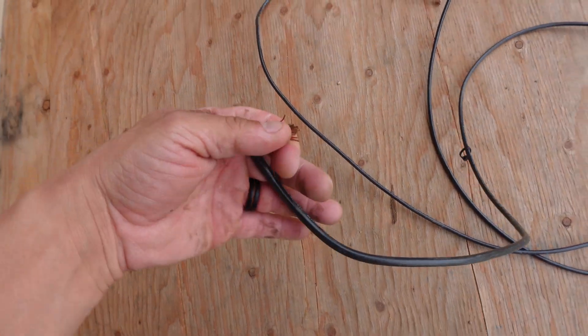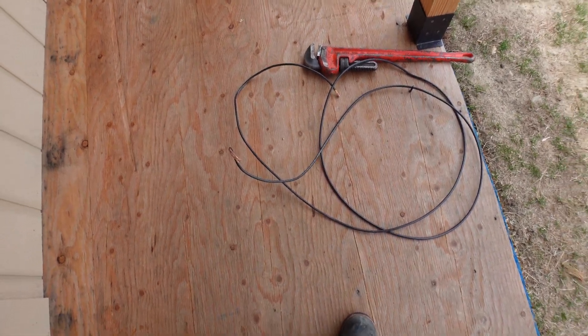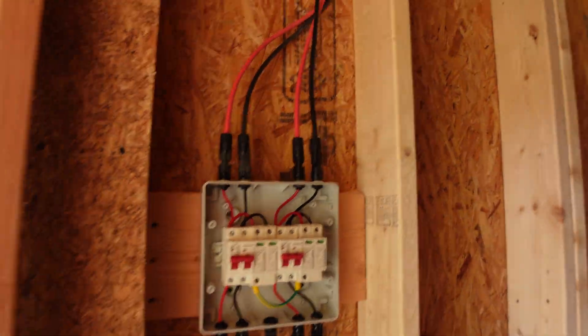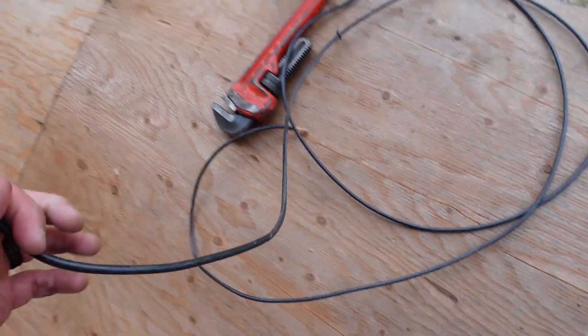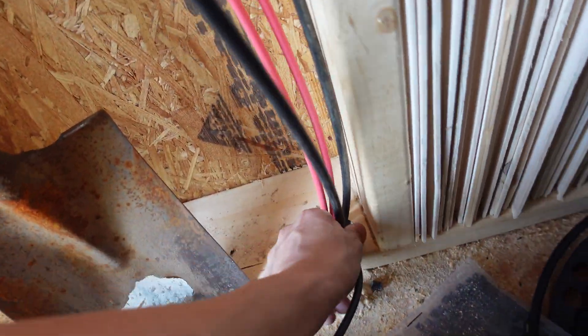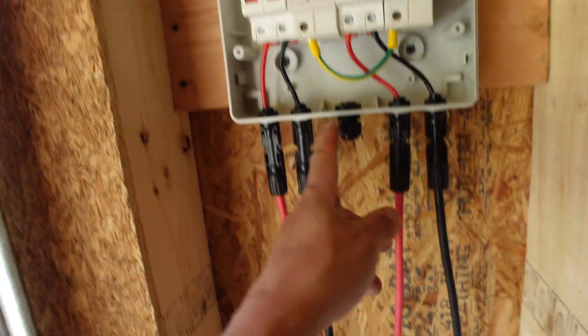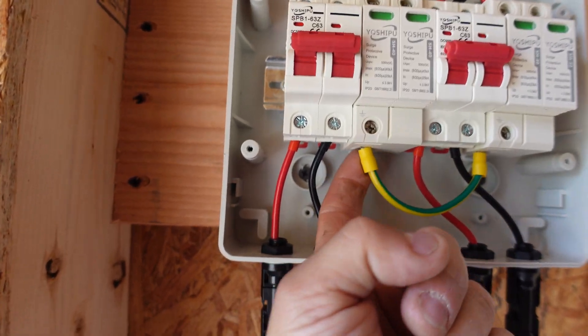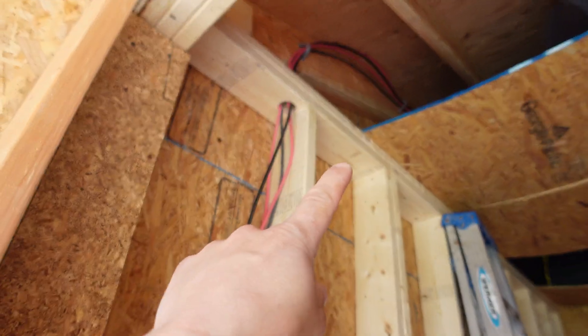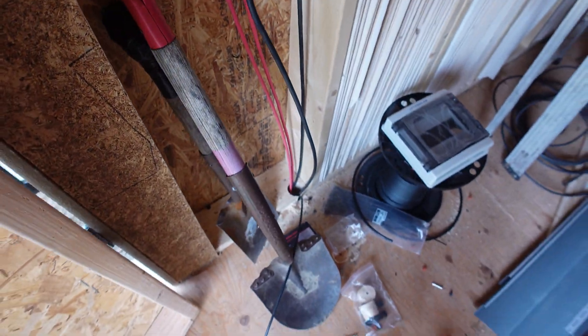Now I'm going to reutilize this wire right here. I think this is six gauge — that's actual ground wire that you would wire a water meter with. If you guys don't know, I'm a plumber by trade. I still need to clip these lines and cover that hole. We're going to get this wire through the base here so I can land it on the ground rod, then pull up the rest coming into the bottom grommet here, landing into the base of this surge protector. I also need to run a ground from the panels up top down the side and loop it into the box as well, tying into the wire hitting the ground rod, so everything is completely grounded.